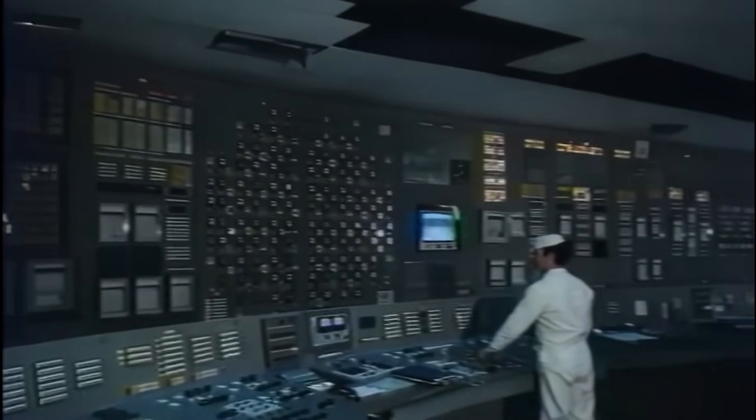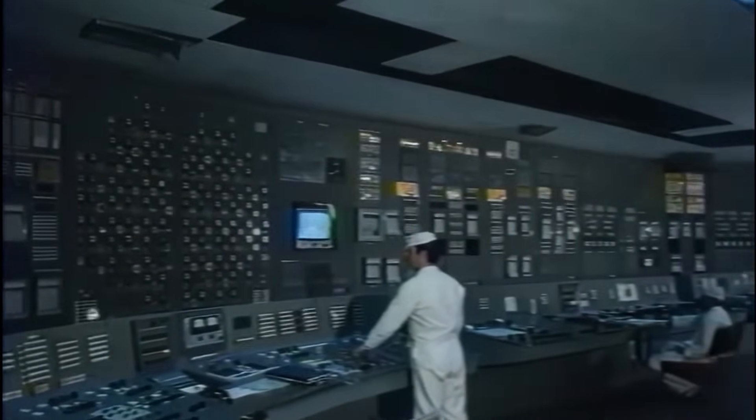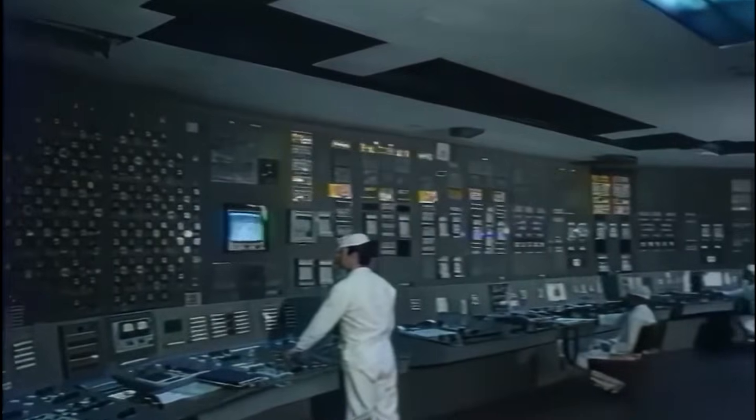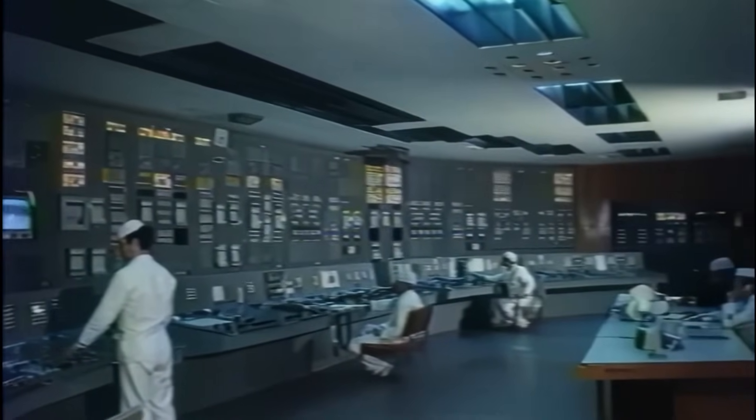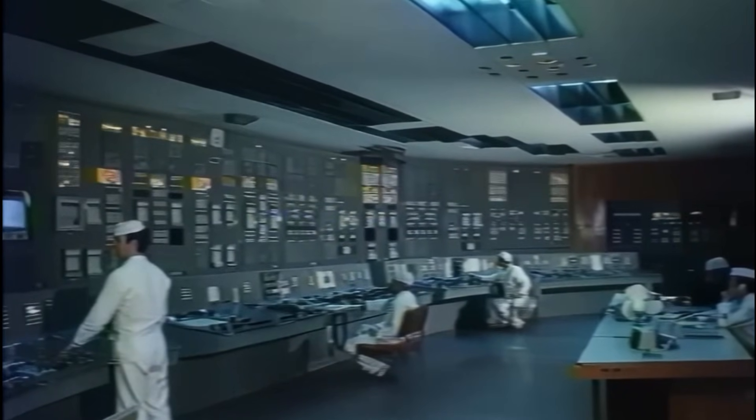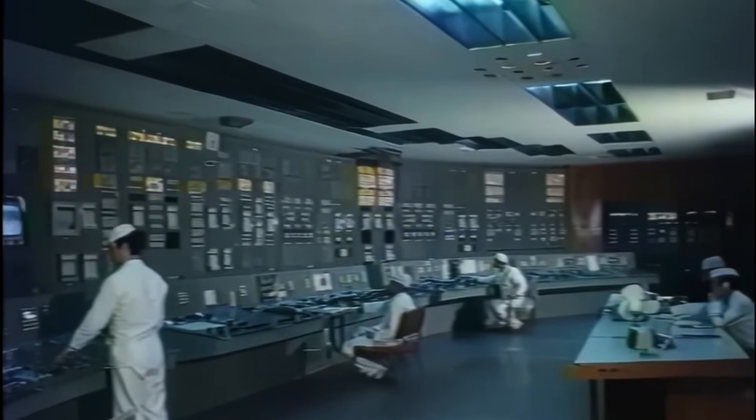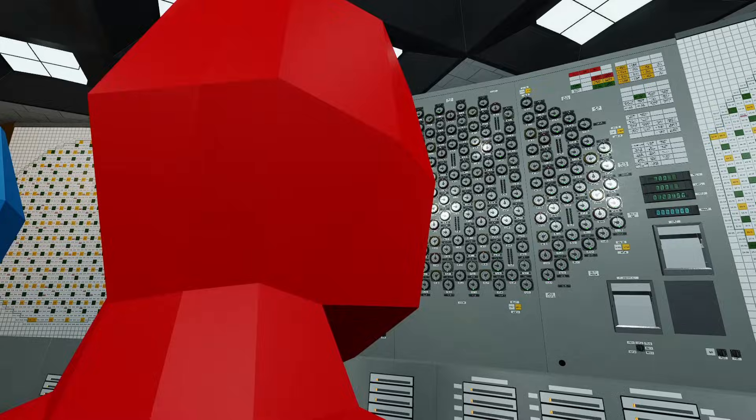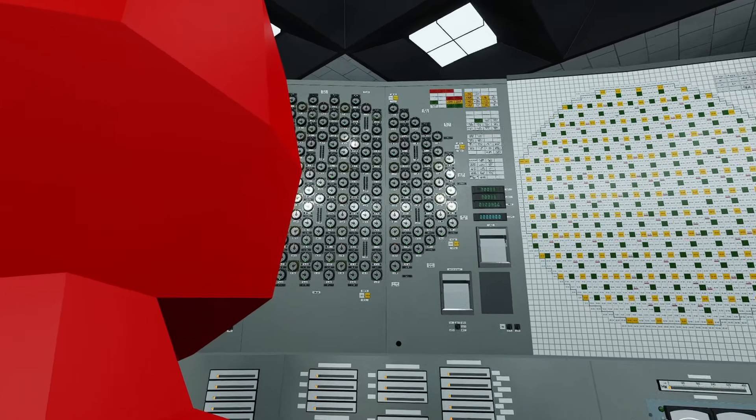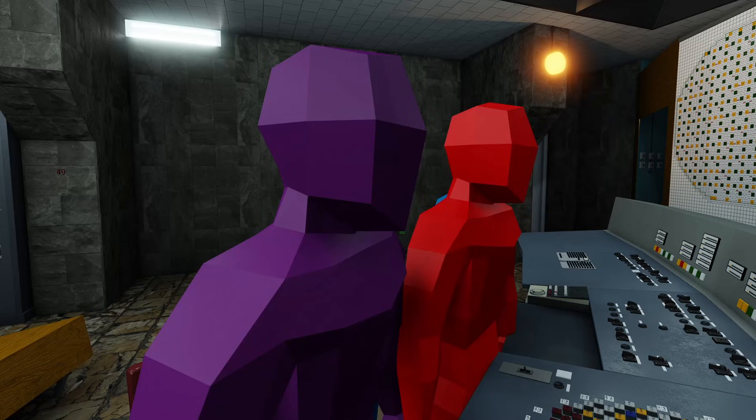Despite the fact that operators could only rely on the side ionization chambers to estimate power, this mode of operating had never been limited or forbidden by the designers or engineers that created the RBMK. The operators did reportedly have some mechanism of drawing up a rough operating reactivity margin in the control room, using a slow data recording system that would bring the value up on a display, which Toptunov checked semi-regularly against hundreds of other data points to keep the reactor in balance. Tregub too looked and saw a number around 19, and slowly dropping down, but still clearly above the minimum limit. A lot of these inserted rods seem to be the automatic regulators counterbalancing the rising positive void coefficient.